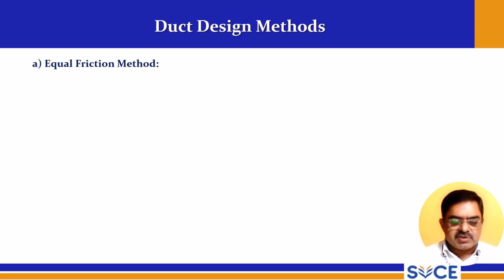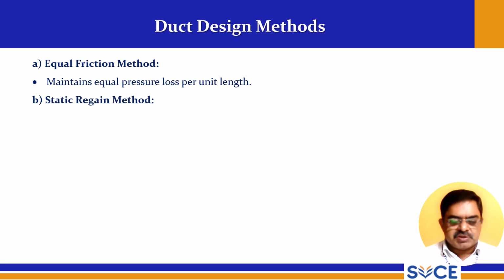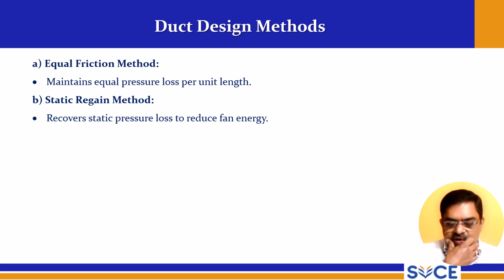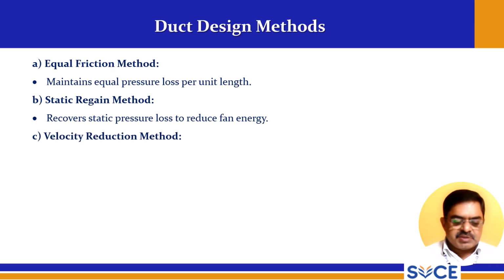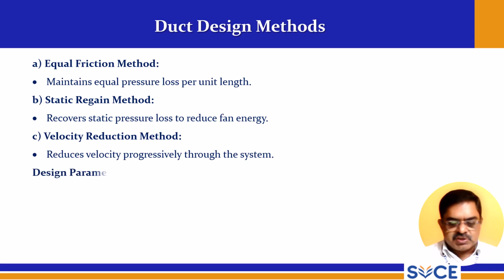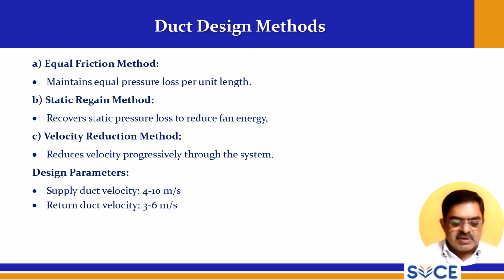So, duct design methods. The equal friction method maintains equal pressure loss per unit length, and the static regain method recovers static pressure loss to reduce fan energy. The velocity reduction method reduces velocity progressively through the system. Design parameters: supply duct velocity 4 to 10 meters per second, and return duct velocity 3 to 6 meters per second. Pressure drop is 1 to 2 pascals per meter.